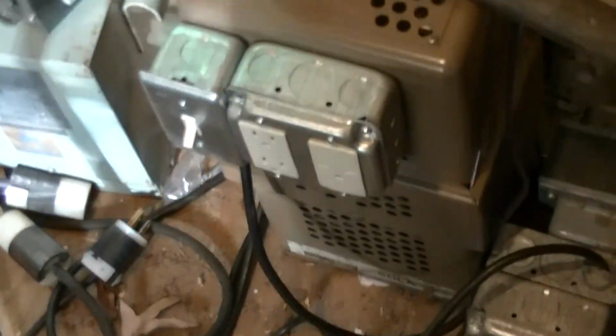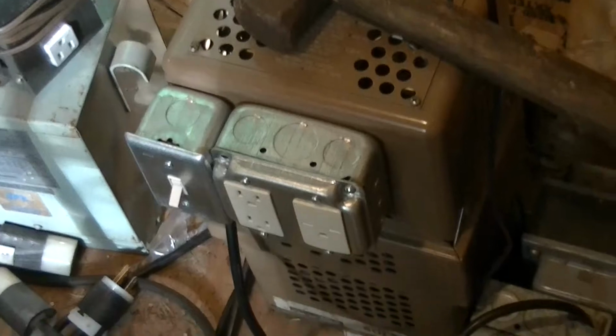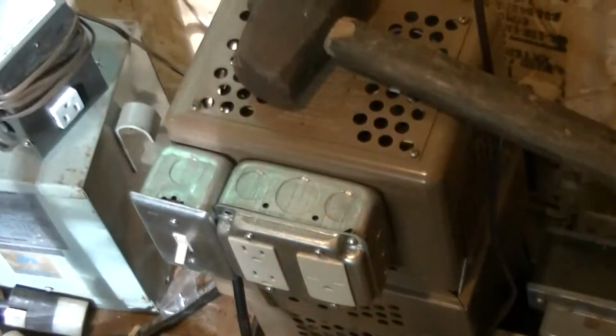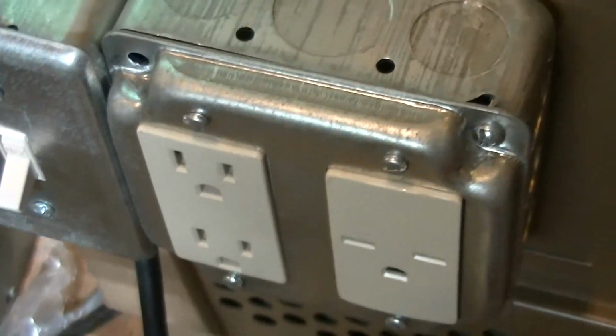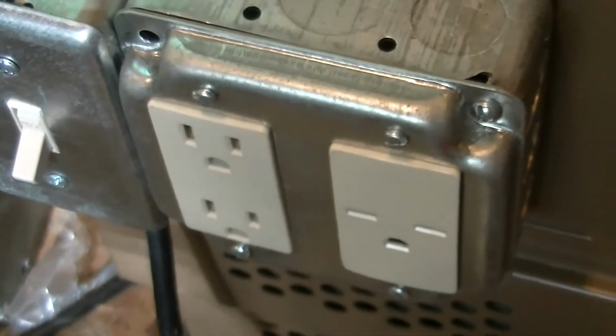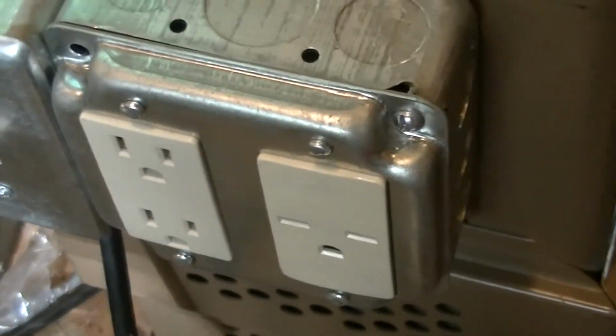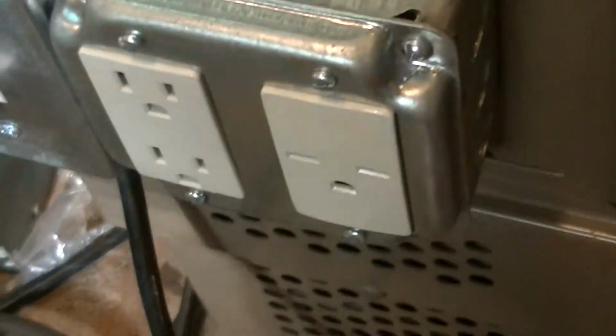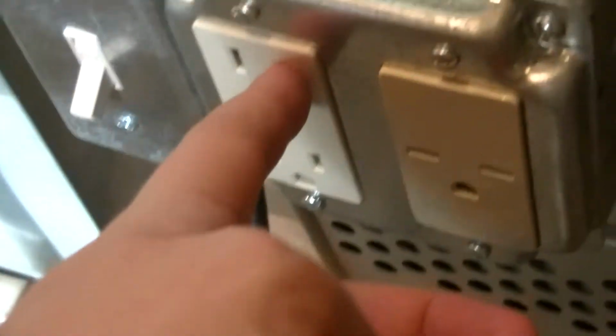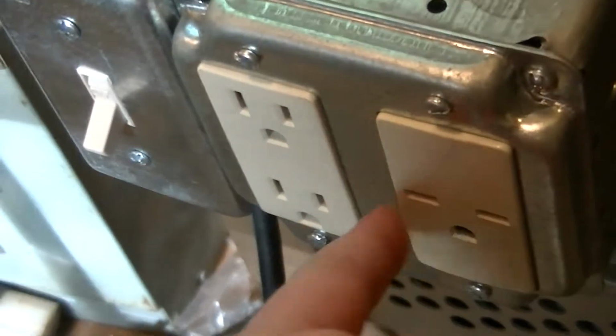Then there's this, which is a somewhat more complicated, substantially bigger transformer. This one is 1 kilovolt ampere. One interesting thing about this guy is that the output winding is a fixed split phase 120 volt, 240 volt winding, thus the pair of 120 volt receptacles as well as a 240 volt receptacle.